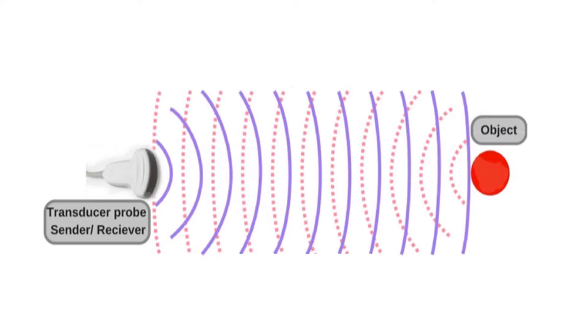You would think that the big heavy part of the ultrasound machine does most of the work, but no. The real MVP here is the probe, or the transducer. The probe almost simultaneously generates and receives ultrasound waves. The ultrasound probe has many small crystals underneath its surface which, upon receiving an electrical stimulus, vibrate and generate ultrasound waves.